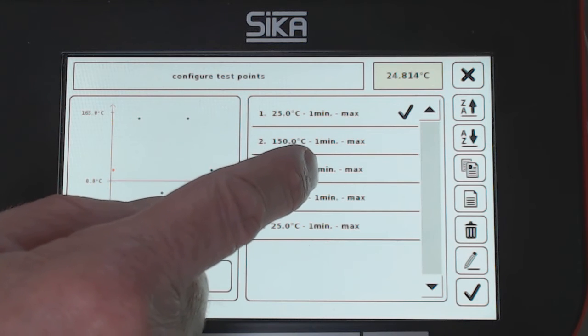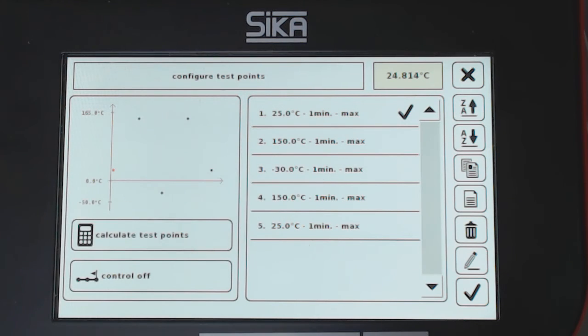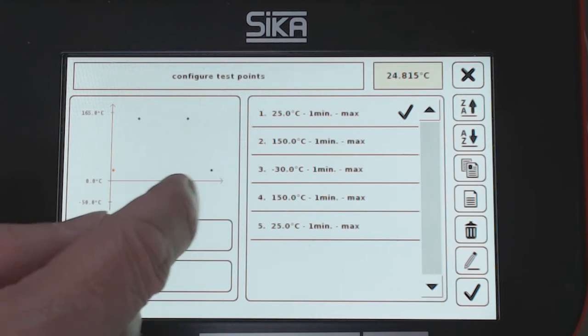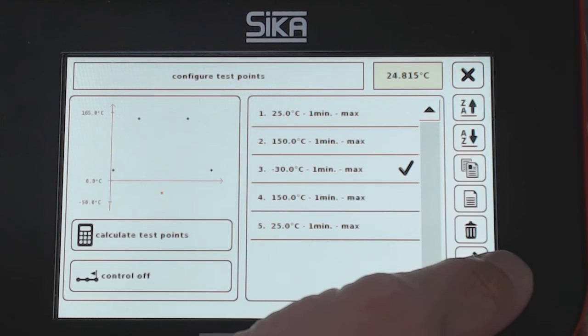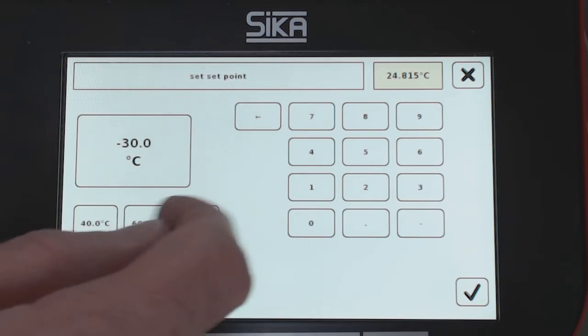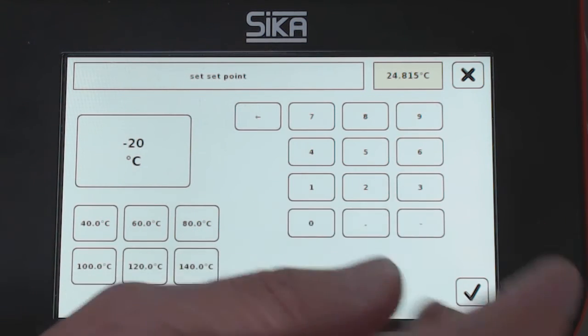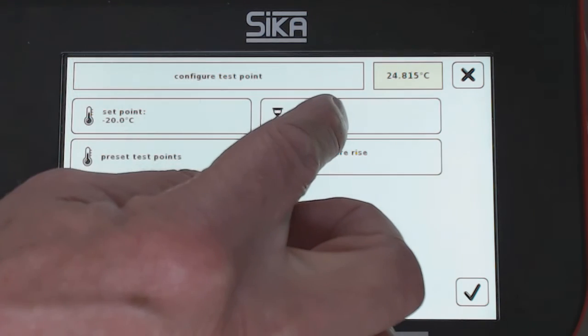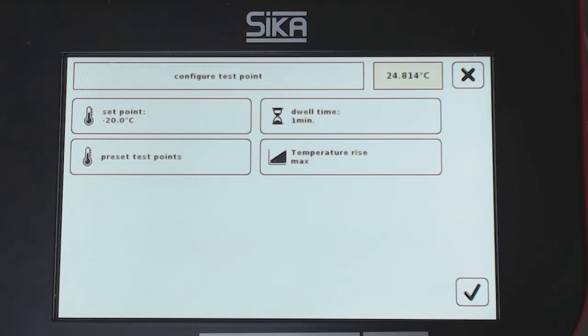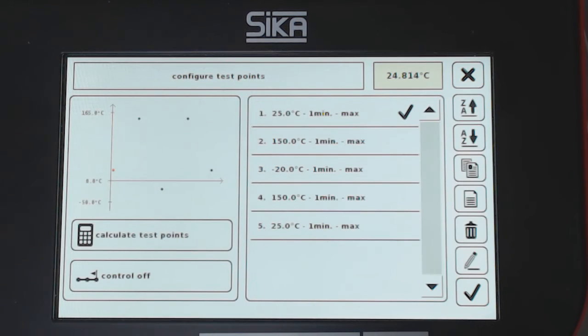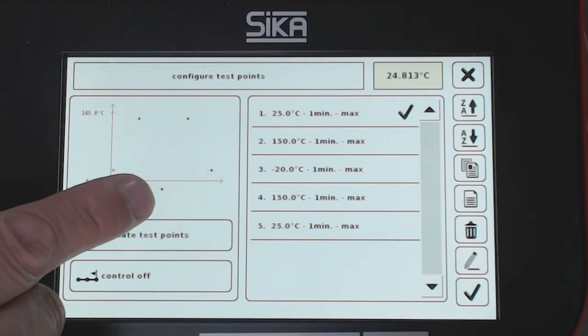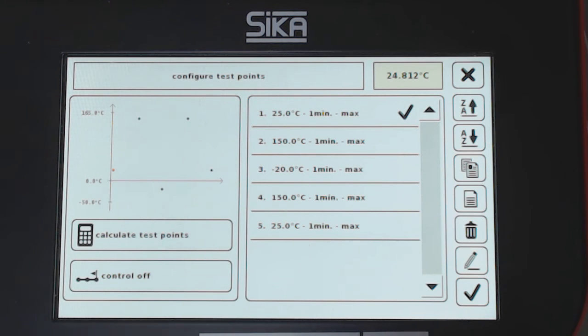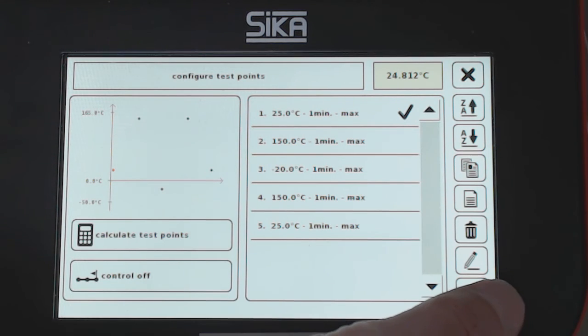Maximum speed. The complete setup for the test point is done. Also, the temperature of the surface is limited in the negative range — this is limited to minus 20. I edit this value to minus 20 and confirm. Dwell time: 1 minute, maximum speed. The complete test points are: 25, 150, minus 20, 150, 25. That's the test point curve.